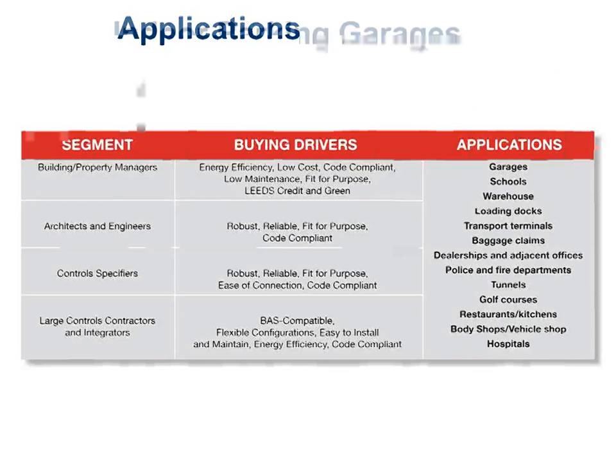But if for some reason you were expecting that, you're doing a parking garage in Europe and diesel cars are common, okay, different rules. Or you're doing a parking garage somewhere where you're expecting a lot of pickup trucks and dualies and all that, okay, maybe you need to do it as well. For carbon monoxide, our typical TWA, my 8-hour maximum, is 25 parts per million. So when I get to 25 parts per million, at that point in time, I want to do something with the ventilation system. Either turn more exhaust fans on or ramp my exhaust fan up, that sort of thing.